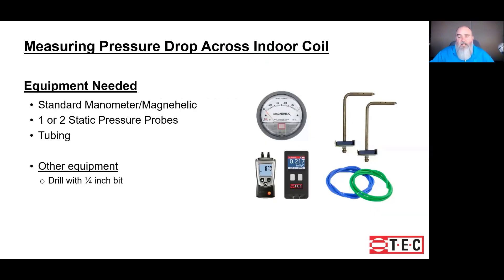The equipment needed to perform this test is not much. We need a Magnehelic gauge or a digital manometer. It's not a test that requires a real precision instrument — any of these will do the trick. We definitely need a static tip and a hose; two is preferable, but one is more than adequate. And we need some way to drill into the equipment.